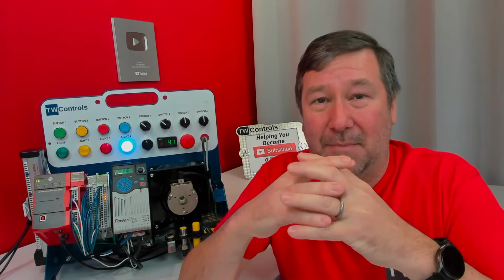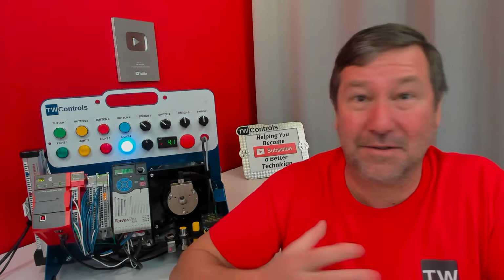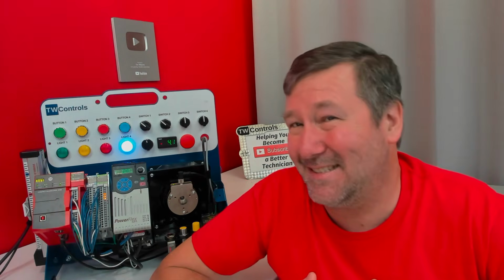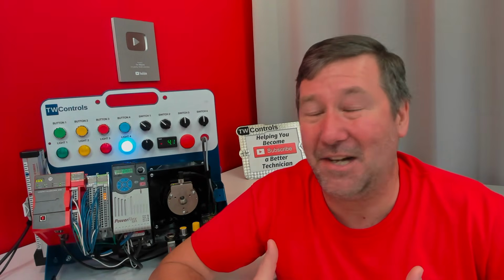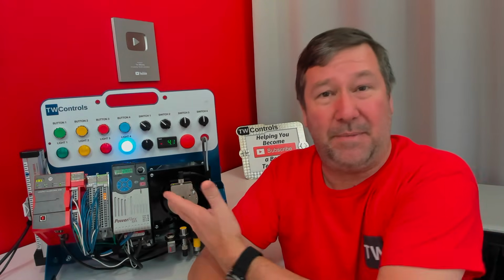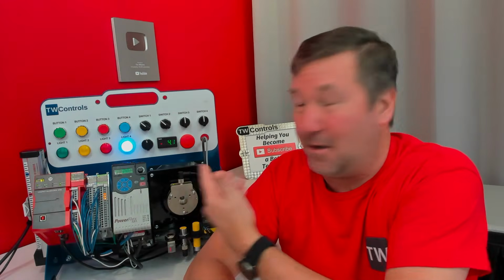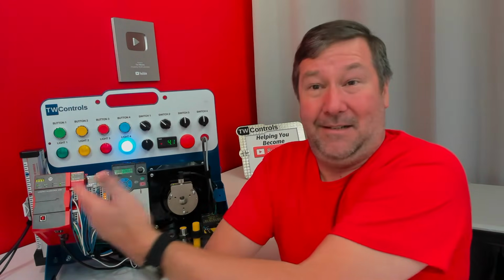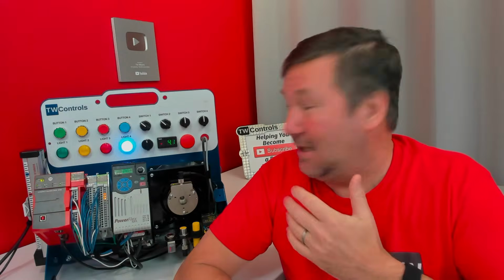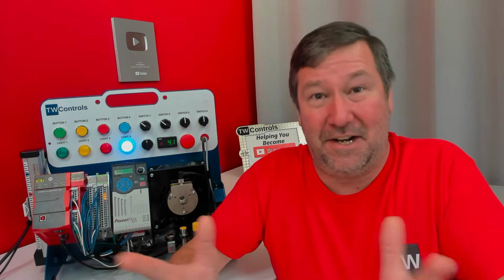But what I'm going to point out is notice here, this first module is labeled as Input Module 1. The second one is Input Module 2. The third one is Input Module 3. I already know it's Module 1, Module 2, and Module 3. I can see that in the IO configuration. At the point we're looking at this module, we need to know something to help us figure out what's going on, either in the field or something. So the best description I see on modules somehow connects us to the wiring diagram. Even if we name it PLC trainer, that doesn't help us any. We already know it's a PLC trainer. We already know it's an input module. But somehow associate it with something.